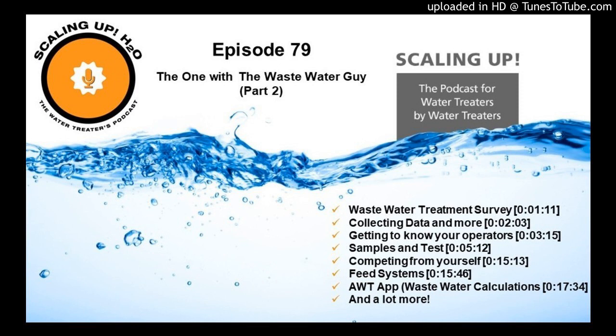Second step then is coagulation. I go through the exact same chemicals every time. I start with the organic chemicals, then I go to the inorganic chemicals, coagulants. Then I go to flocculants. I look at the different charges, which is the best charge. Then I work to best charge density and best molecular weight. I do it the same way every time. And everybody has their own way of doing it. I'm not saying mine's right. This is what works for me.